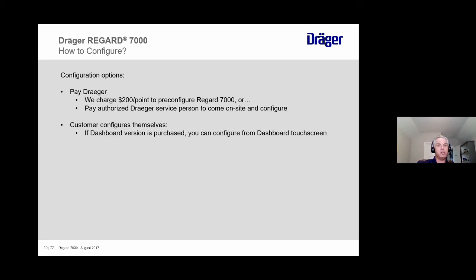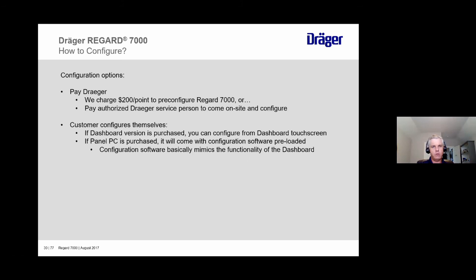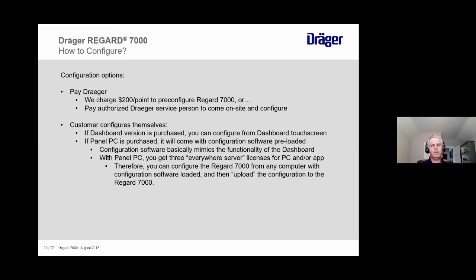Or the customer can configure it themselves. If the dashboard version is purchased, then you would configure through the dashboard touchscreen. And of course, if the panel PC option is purchased, it will come with the configuration software preloaded. That configuration software basically mimics the functionality of the dashboard. With the panel PC, you get 3 everywhere server licenses for that PC, so up to 3 different logins to get into it and make changes. Therefore, you can configure the Regard 7000 from any computer with the configuration software loaded onto it, and then upload the configurations to the Regard 7000.